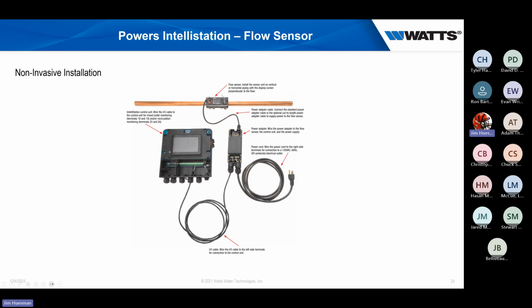Because that flow was screaming through that return, we started getting a lot of pitting. So we added a flow sensor, but on that job we actually had to do a shutdown at 2 in the morning to cut this all in, to put that flow sensor in the return or into that mixed out. Now we're able to jump in, just clamp something on, wire it directly in, and get pretty accurate information on how much is being flowed through that device. It's very simple — we wire it directly in, plug it into our 110, clamp it on the pipe, and get those readings directly back.